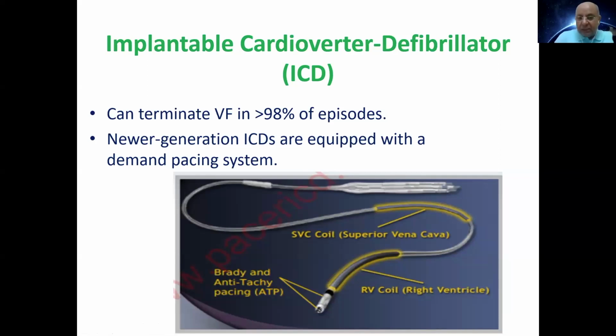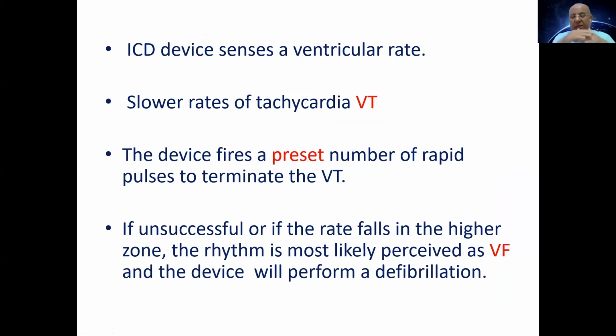It will sense the ventricular rate, and it is programmed. If the upper limit of the normal rate is, for example, X, and the rate increases above this, it will sense it as tachycardia, ventricular tachycardia, and start to give a very small preset number of rapid pulses to terminate the tachycardia, VTAC. If it is terminated, okay. If it is not, or the rate increases, it will sense it as ventricular fibrillation. It will give a shock wave.